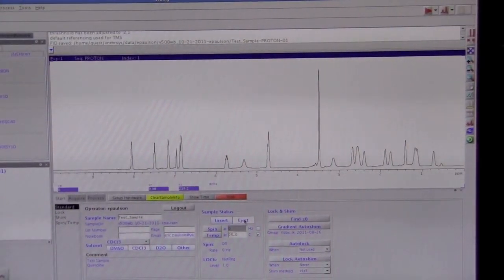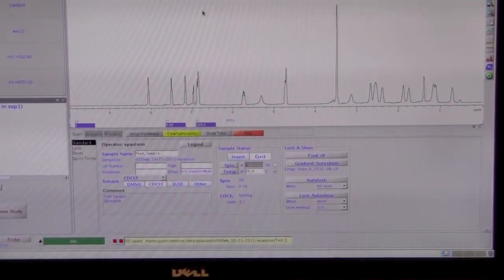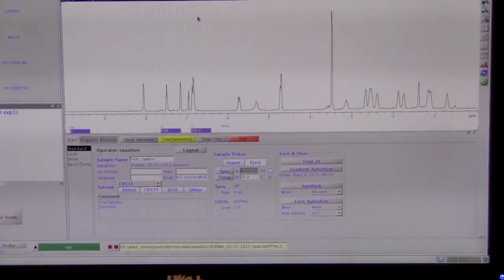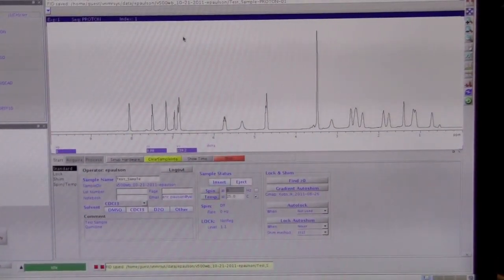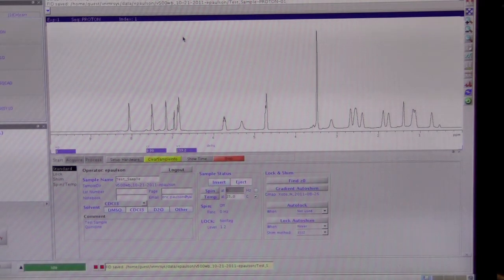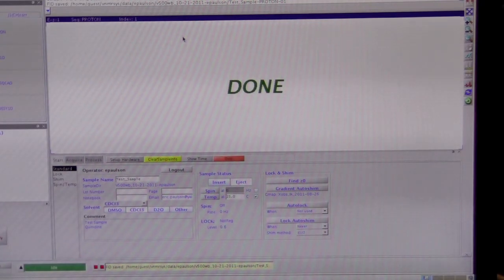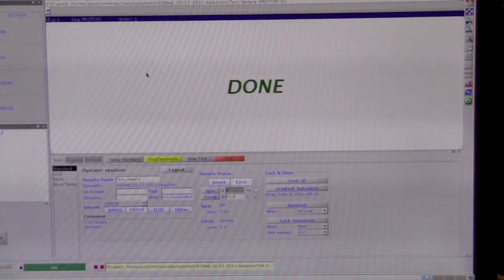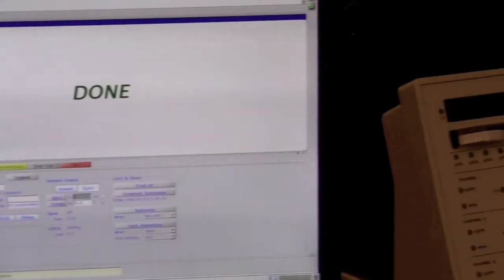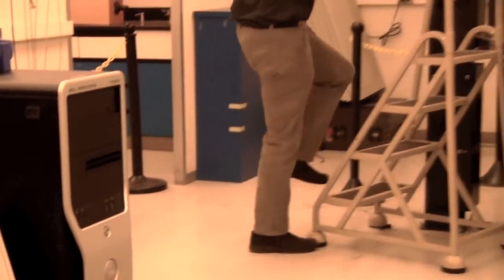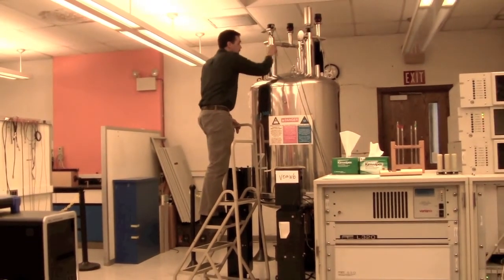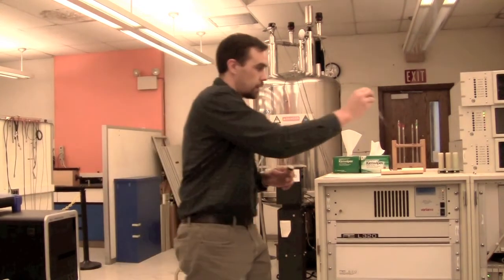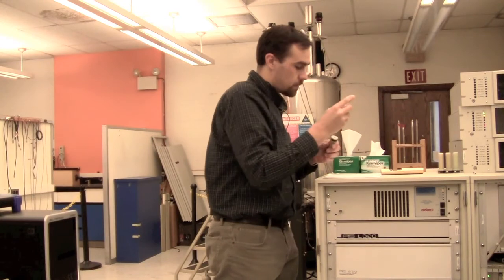And eventually it should eject our sample so that we can put back the dummy sample. I'm going to go ahead and get up and wait for it to get ready. There it goes. There, so it's done. I may want to try clicking eject one more time. Okay, sample's ejecting. Get your sample.